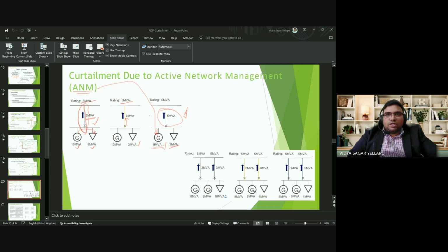This is another example requiring further insight. Here there are two generators, each of 8 MVA rating. This is a 10 MVA load, and the assets are rated at 5 MVA each. There are two parallel assets, 5 MVA each. In this case, for this snapshot of the generation and demand scenario, there is 16 megawatts of generation and 10 megawatts of demand. Excess generation is 6 MVA. The 6 MVA gets shared between these two lines, so each carries 3 MVA. So it leads to a favorable situation.